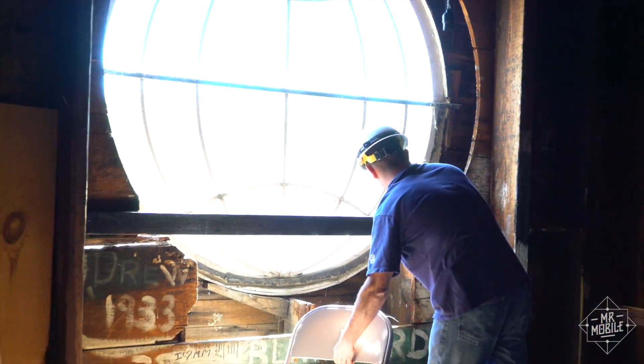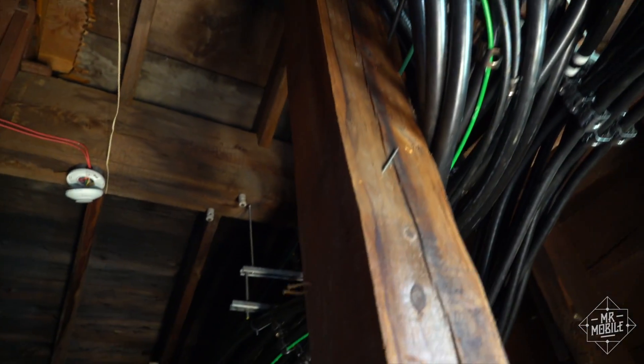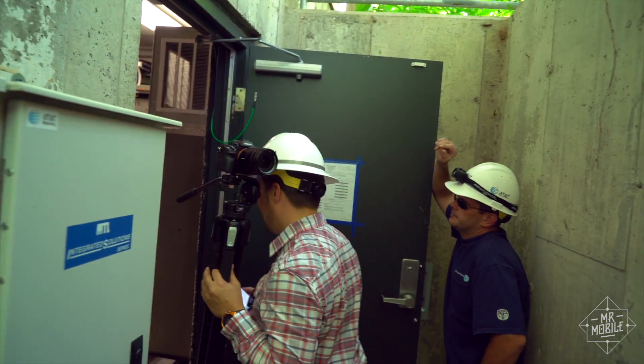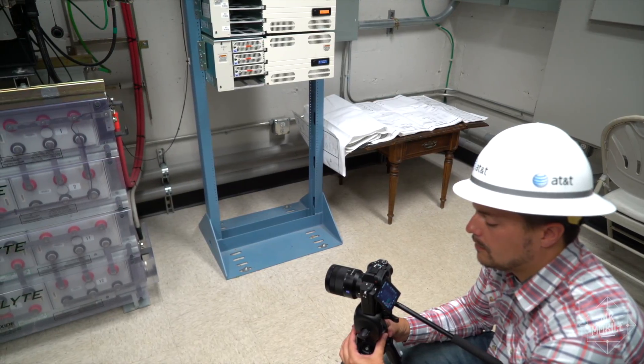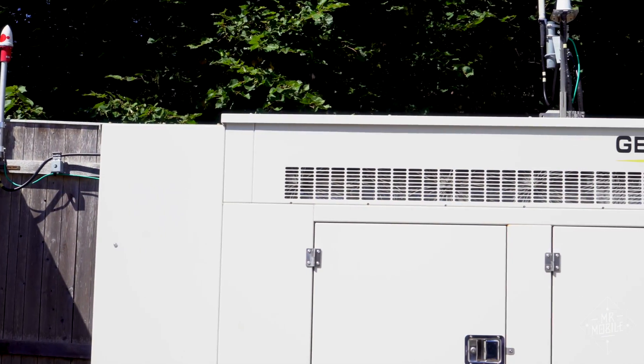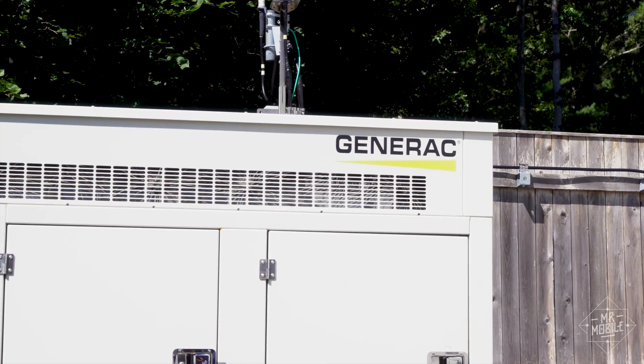But the radio side is just part of the story. The data packets that flip back and forth when you send a text message or subscribe to a YouTube channel have to traverse the internet, and to get to it, landlines are still usually the most efficient way. So we follow the conduits back down the steeple, through the church, and out back to the equipment shelter — basically a concrete shack where the connection to the landline network happens. This is called backhaul, and these days it's all done with fiber. If the power goes out, a rack of lead acid batteries provides an uninterrupted power supply, and there's also a diesel generator outside with enough fuel to power the site for about a day — generally more than enough to last through a storm in this part of the country.